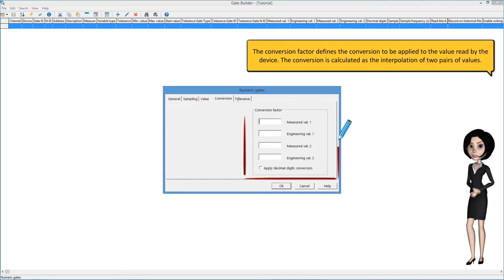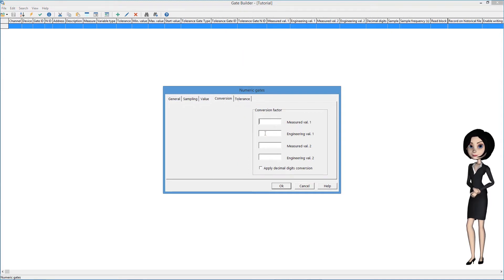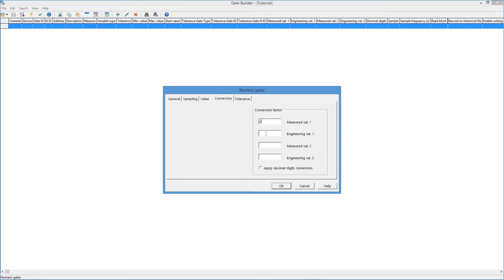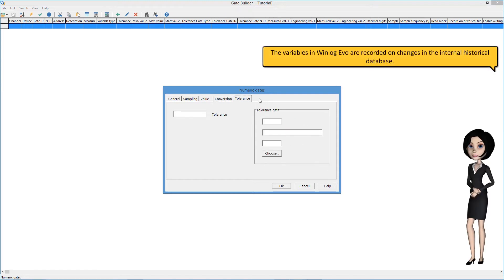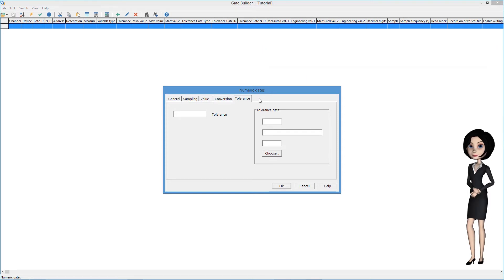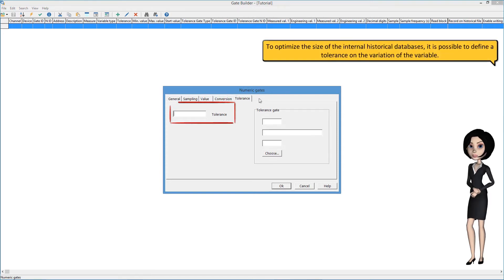The conversion factor defines the conversion to be applied to the value read by the device. The conversion is calculated as the interpolation of two pairs of values. The variables in WinLogEvo are recorded on changes in the internal historical database. To optimize the size of the internal historical databases, it is possible to define a tolerance on the variation of the variable.